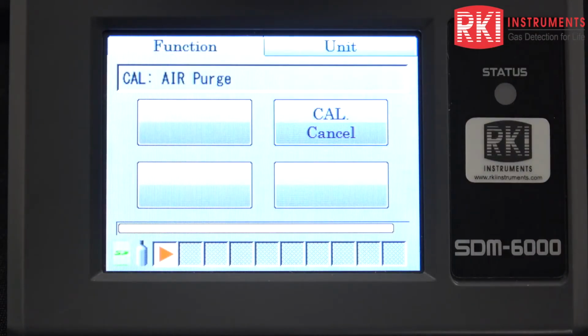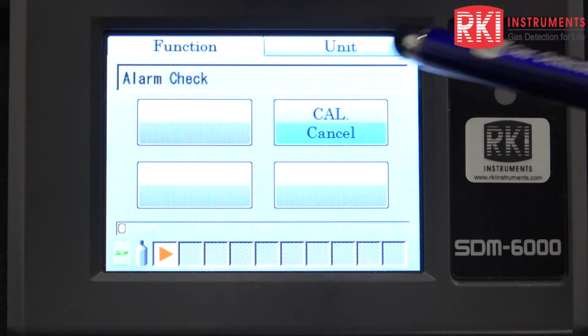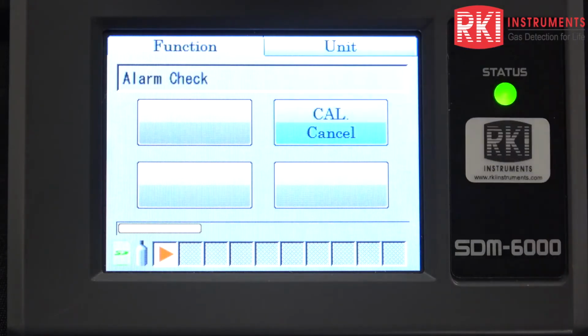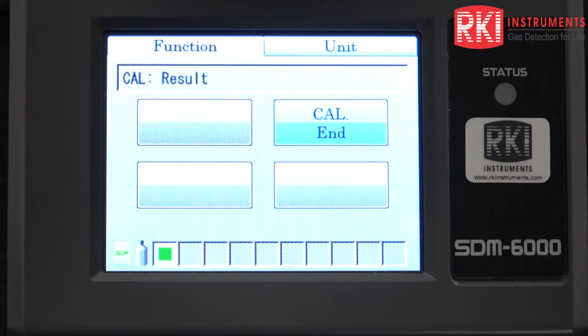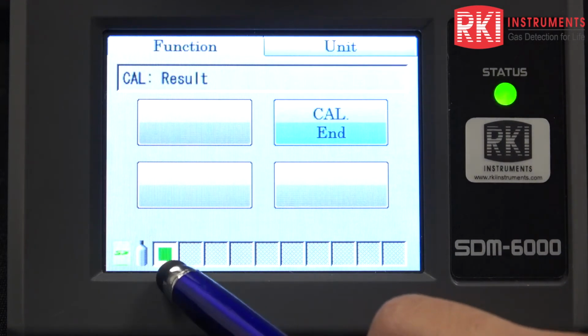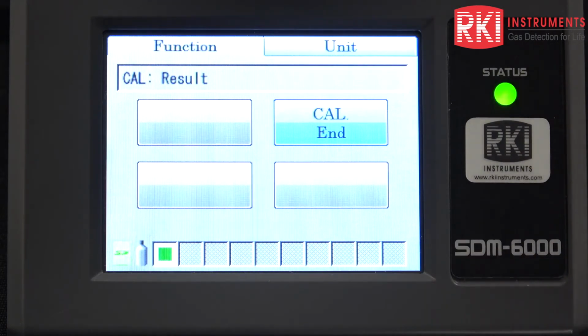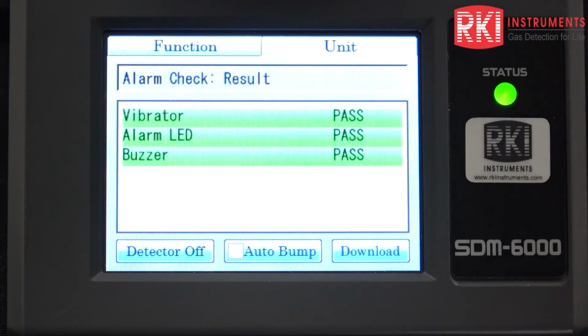And we'll go back to the function tab here. You're going to see a little progress bar right there. It's doing an air purge right now. And you can cancel your calibration anytime. Right now it's doing an alarm check, since I checked that option earlier. And cal end. So you can actually see the results. If it passes, you're going to see that green square. If it fails, you're going to see a red square. If I go back to the unit tab, you're going to see all the passes there. And it does the alarm check as well, since we have that checked.